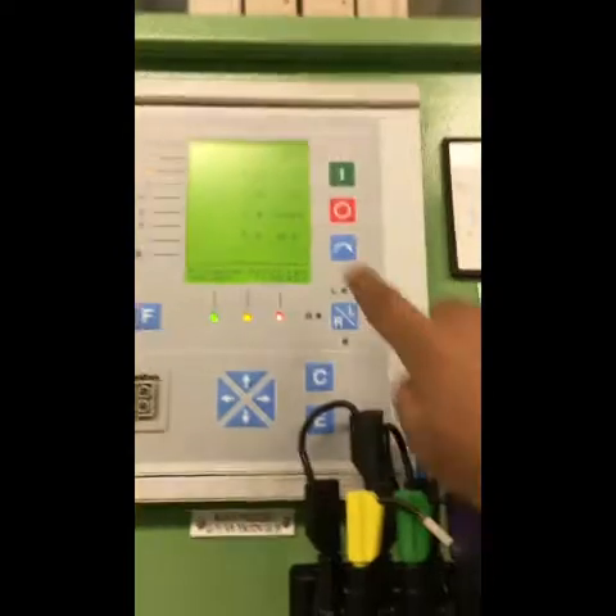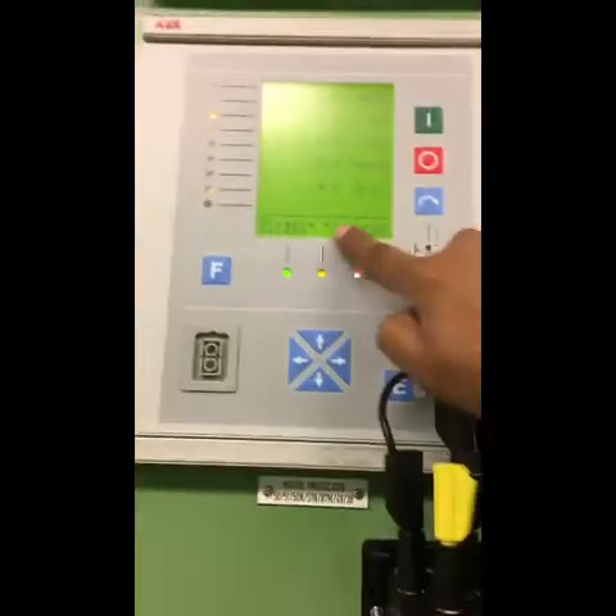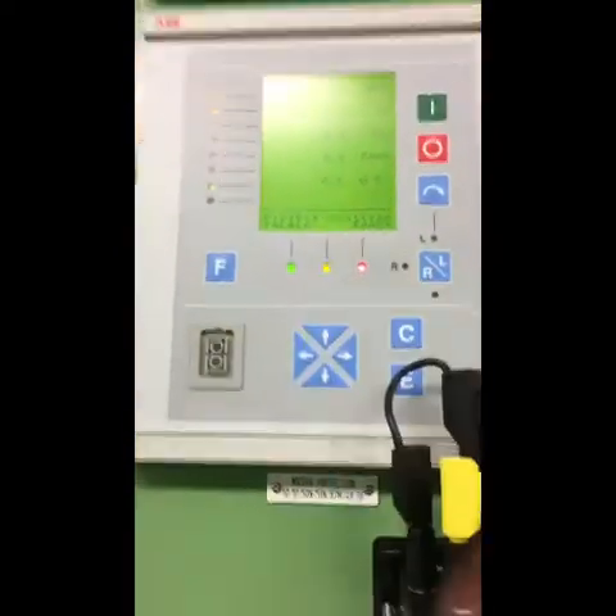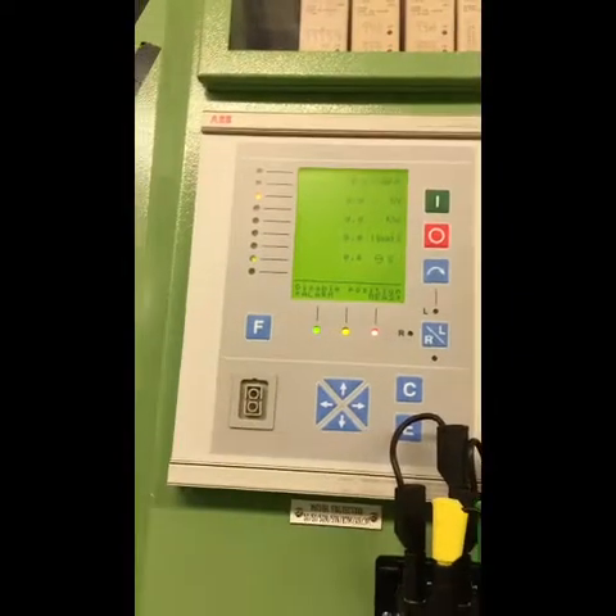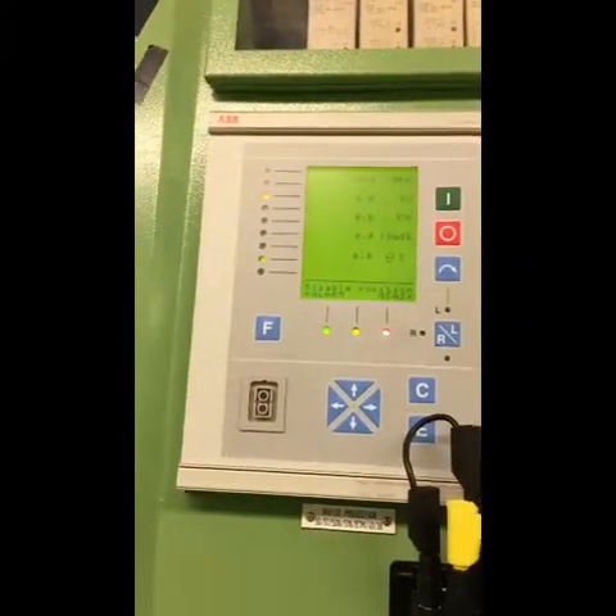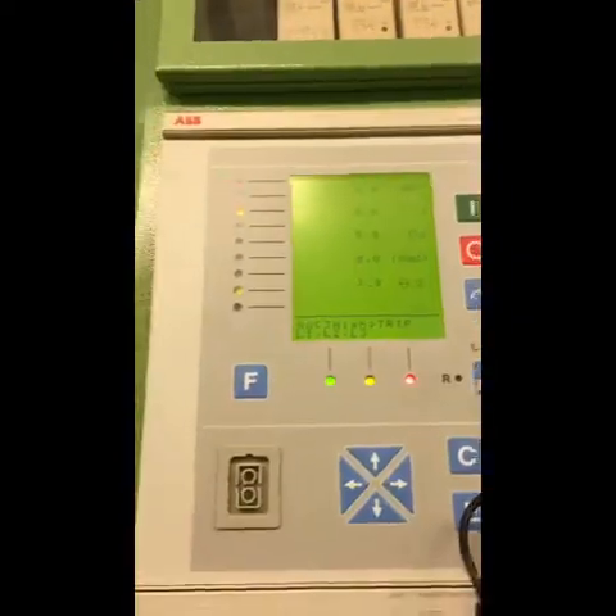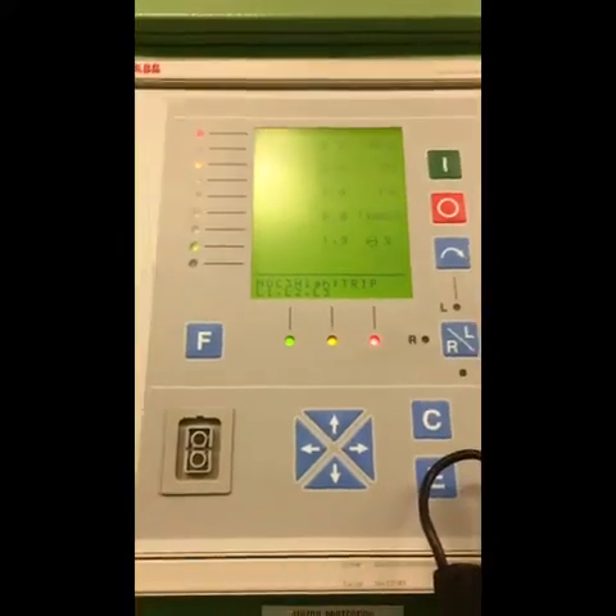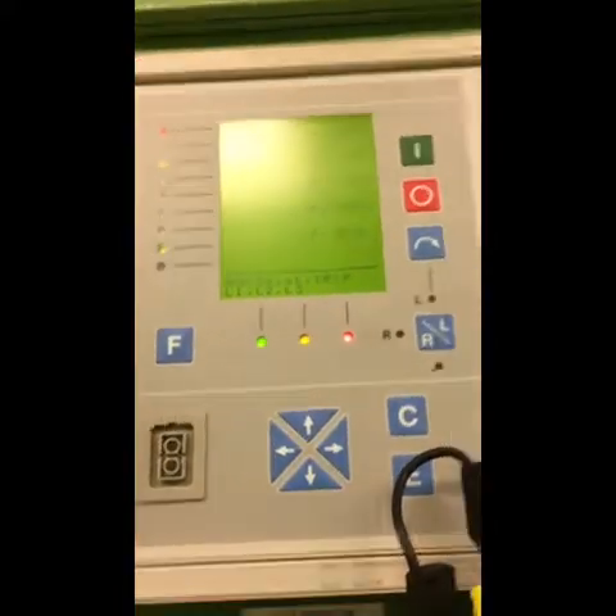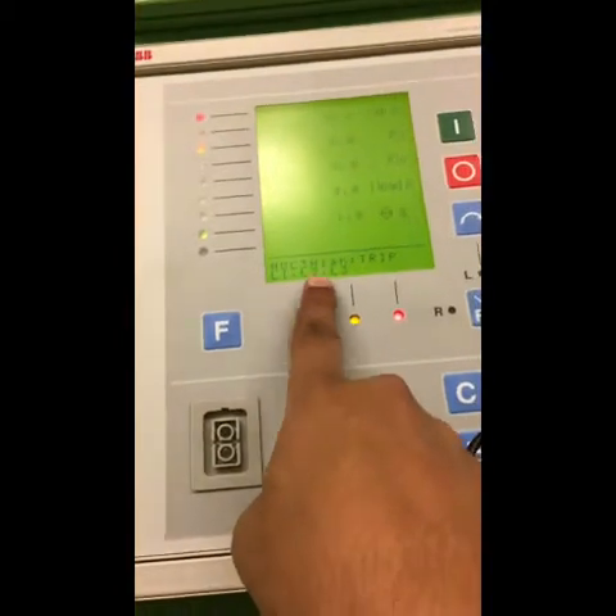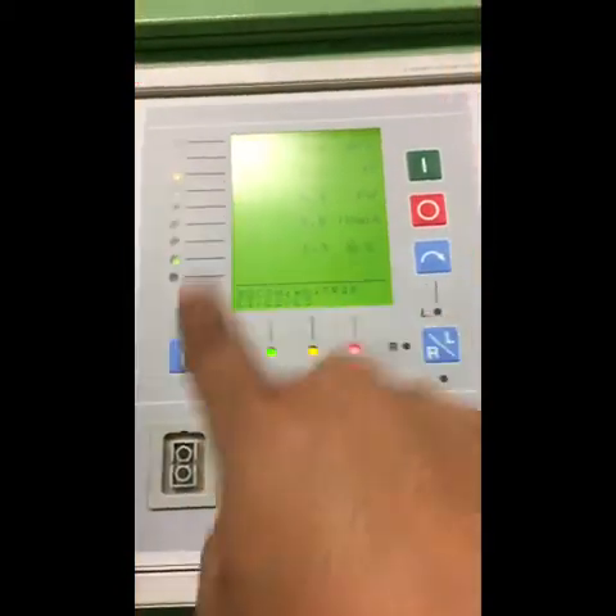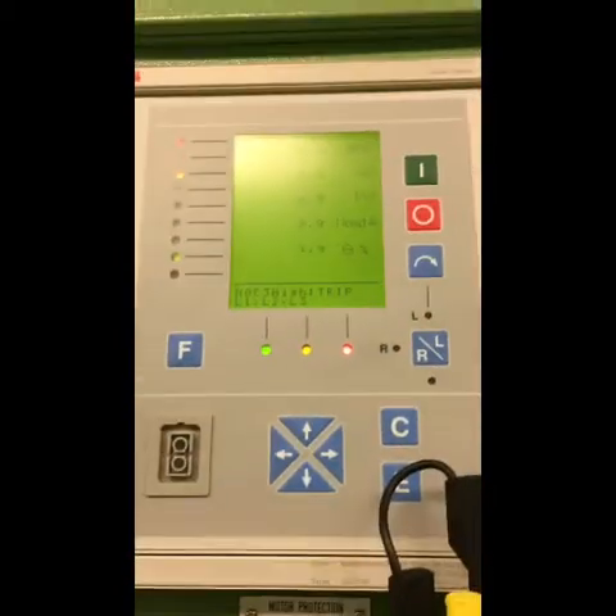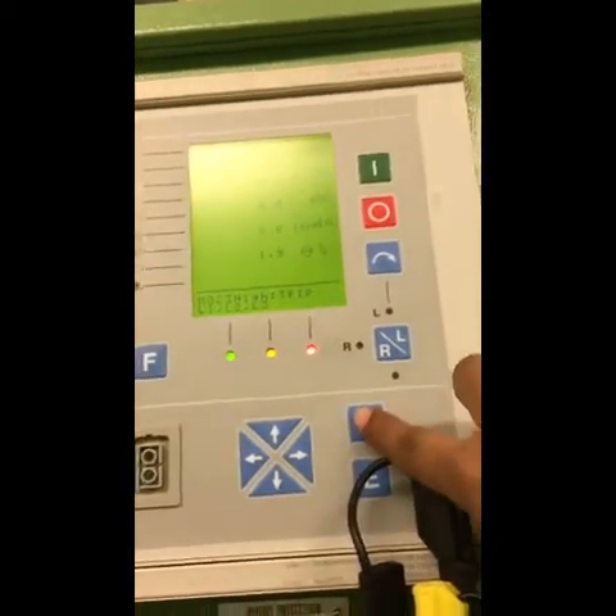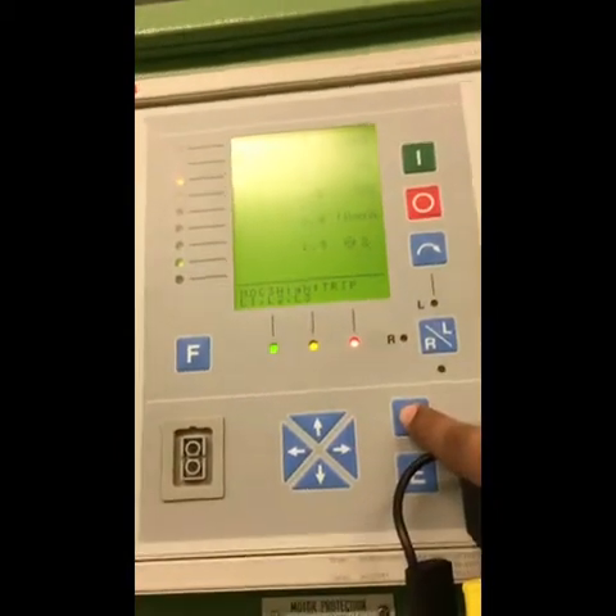If there is any tripping, blinking will show up here, and there will be a trip signal message here. I will give fault current, and you will see it now. Now there is a trip here in this relay, overcurrent trip, and there is blinking here. To reset this fault, I will have to hold here 2 times.